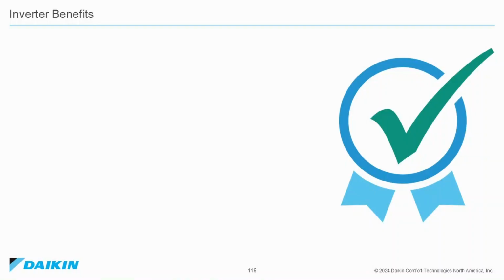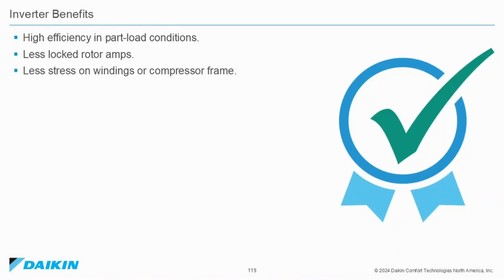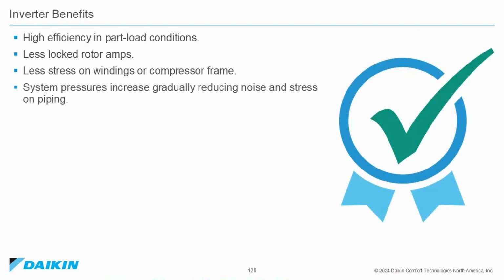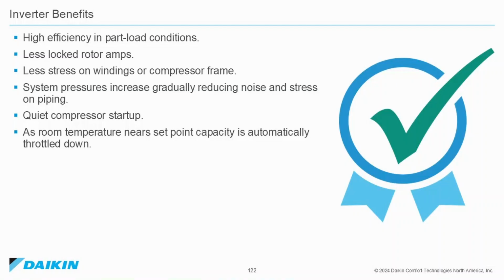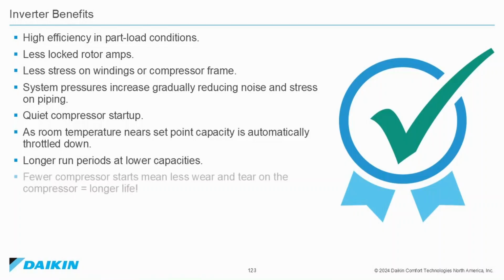Some benefits to an inverter system are high efficiency in part load conditions, less locked rotor amps, less stress on the windings or the compressor frame. System pressures increase gradually, reducing noise and stress on piping. Quiet compressor startup. As room temperature nears set point, the capacity is automatically throttled down. Longer run periods at lower capacities. Fewer compressor starts means less wear and tear on the compressor, which equals longer life.